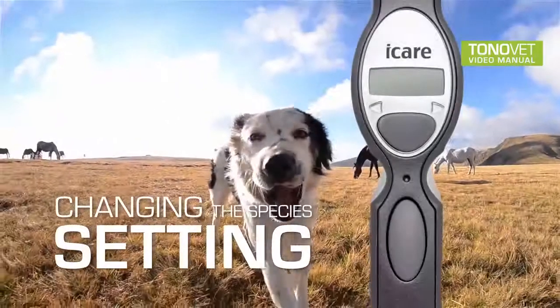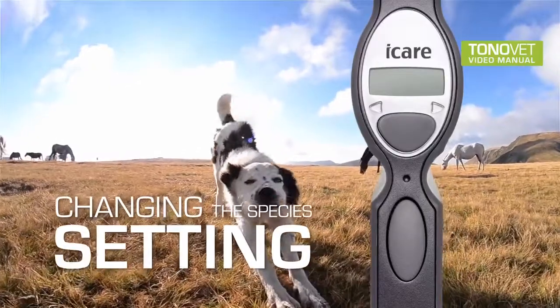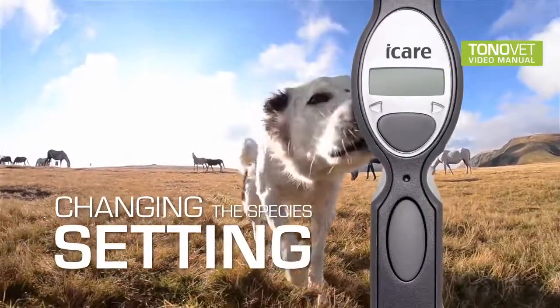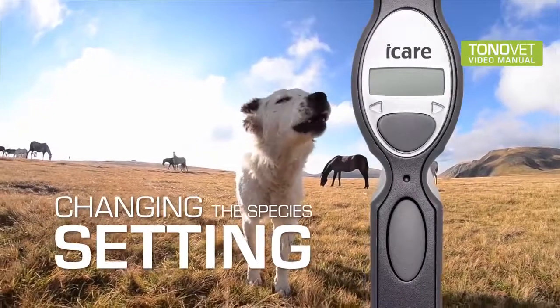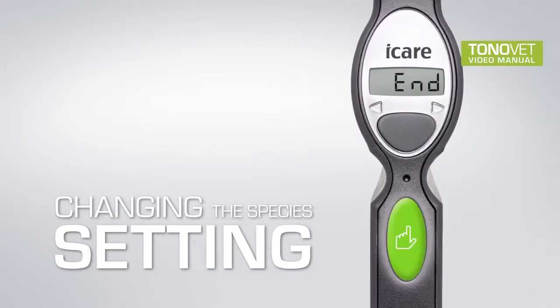Changing the species setting. The TONOVET has measuring settings for dog, cat, and horse. Dog and cat mode is the default setting. To change the settings, press the selector button until the display shows end. Press first the measurement button, keep it pressed down, and simultaneously press the right selector button. Note that both buttons have to be pressed down at the same time.